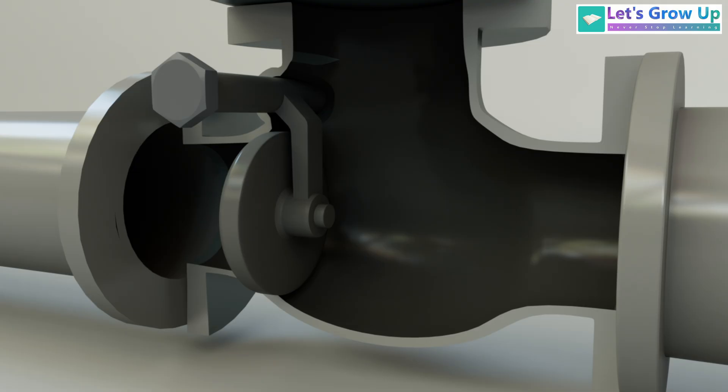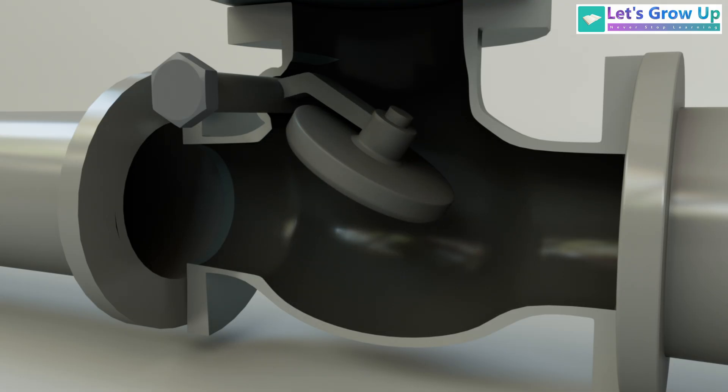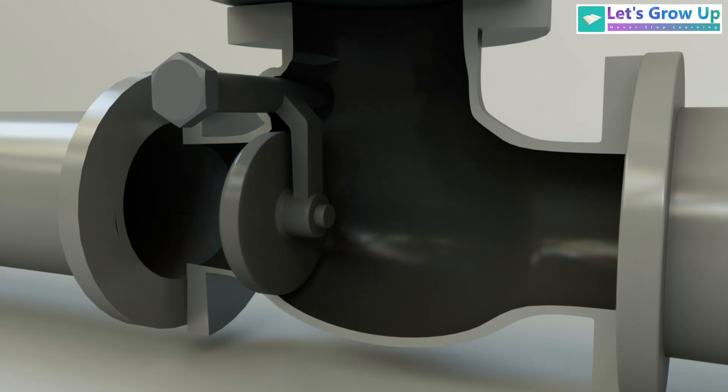When the fluid flows in the correct direction, the pressure pushes this disc open. As long as the flow continues, the door stays open. When the flow slows down or reverses, the disc simply swings back shut due to gravity and the pressure of the backflow, sealing the passage.